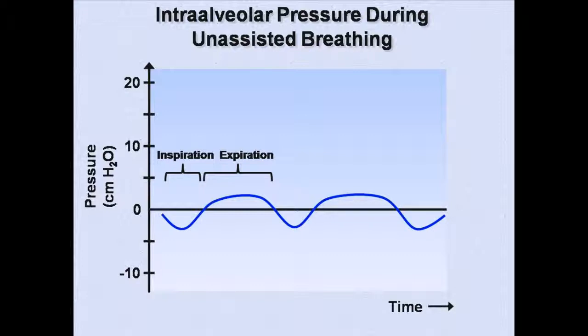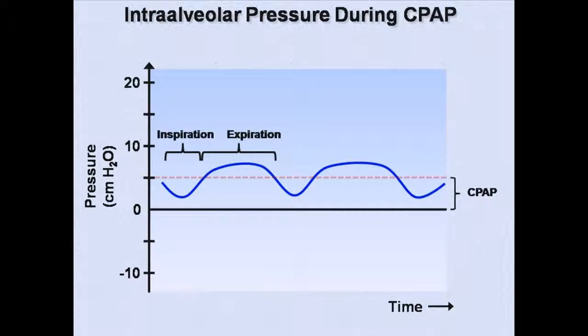In CPAP ventilation, a continuous, unchanging positive pressure is applied to the airways by means of the masks seen earlier. This has the consequence of moving the intra-alveolar pressure versus time curve up by approximately the same degree as the value of the extrinsically applied pressure. However, the mechanics of breathing are otherwise left relatively unchanged. The continuous positive airway pressure acts similarly to positive end expiratory pressure, or PEEP, which is an important ventilator setting. I'm using the approximately equal sign here not to express mathematical equivalence as much as conceptual equivalence. A more complete discussion of the consequences of PEEP will occur in lectures 7 and 8.